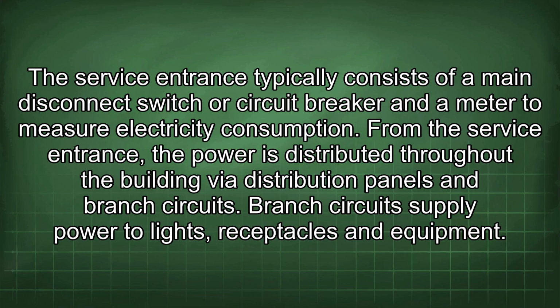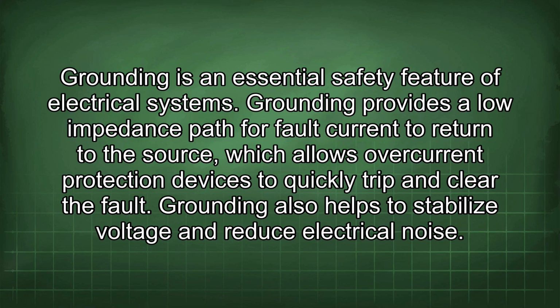From the service entrance, the power is distributed throughout the building via distribution panels and branch circuits. Branch circuits supply power to lights, receptacles, and equipment. Grounding is an essential safety feature of electrical systems. Grounding provides a low impedance path for fault current to return to the source, which allows overcurrent protection devices to quickly trip and clear the fault. Grounding also helps to stabilize voltage and reduce electrical noise.